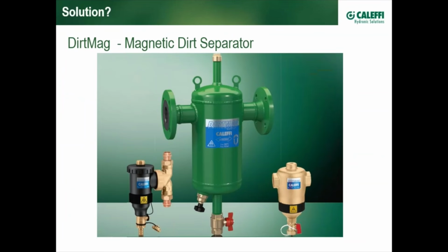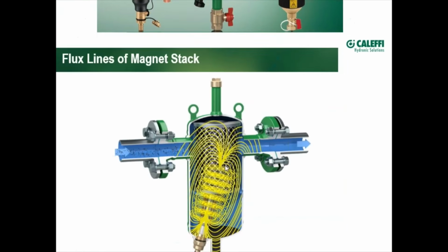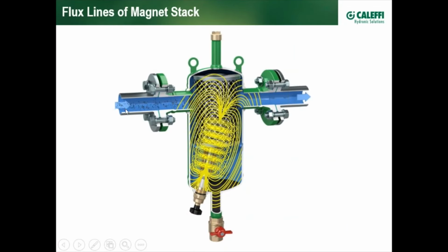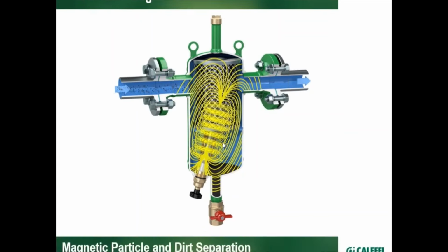So to address that issue, Caleffi developed the magnetic dirt separator. You can see these dirt separators, whether they're small for residential or light commercial or large for the bigger commercial jobs, they all have in common a magnetic force that is in place inside of the system, either by way of an external band with the brass and polymer, or an internal bayonet, if you will, that extends up into the system. So if we were to take this guy apart and see what's going on on the inside, it would look like this. Debris comes in, the yellow indicates the flux lines of the magnetic field. Let's take those flux lines away and see what's going on.